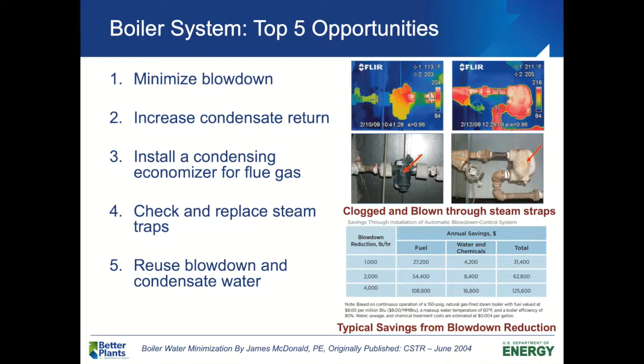With respect to condensate, the first thing you want to look at is making sure you're able to return it back to the boiler house. In cases when you're not able to do it economically, or there are logistic barriers to returning it back to the boiler, you can think about reusing that condensate water for other purposes. This is warm water, so there is some low grade heat available, so you can think about using it in some of your processes or for cleaning operations.